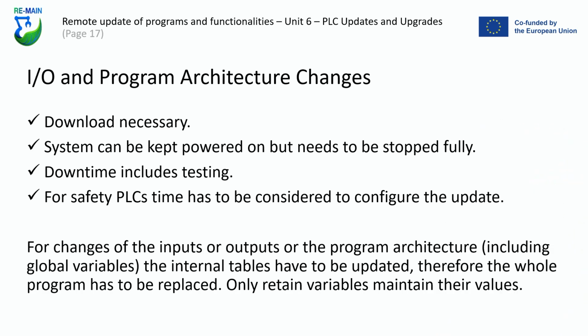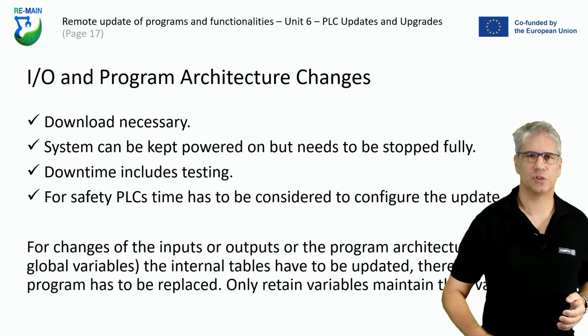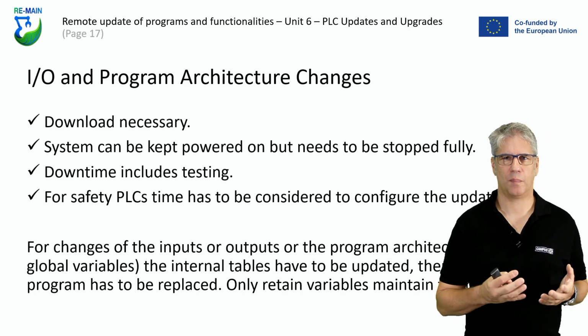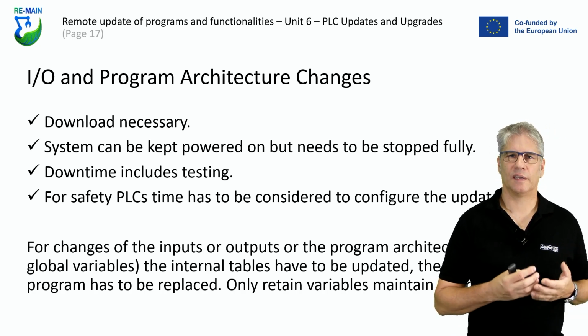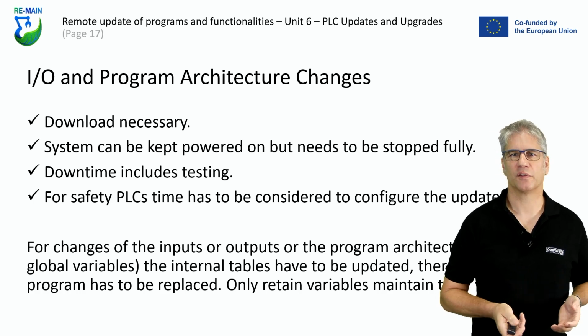The reason for this is that internal variables, if you add some or change them significantly, the whole program has to be replaced. So you cannot do an in-place exchange very easily, because if variables change and their values change, and also maybe their type change, it can happen that the program would crash if you just download it. And normally it's better to have a machine turned off properly and started again, than to crash the machine because of some program failure.